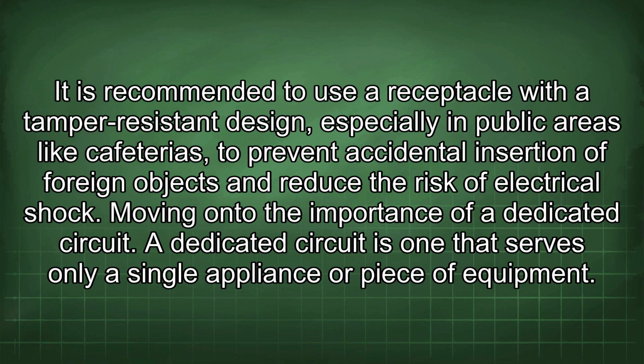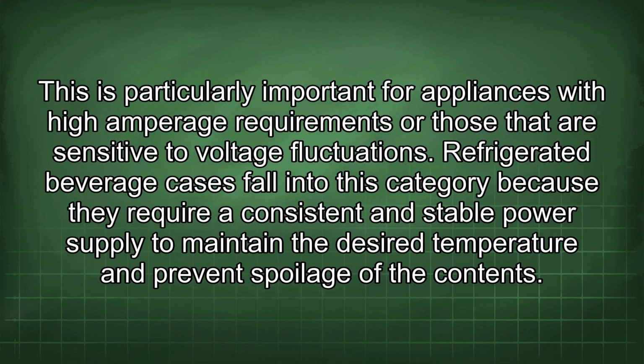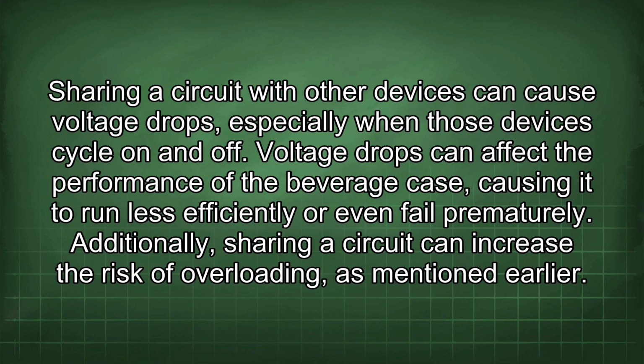Moving on to the importance of a dedicated circuit. A dedicated circuit is one that serves only a single appliance or piece of equipment. This is particularly important for appliances with high amperage requirements or those that are sensitive to voltage fluctuations. Refrigerated beverage cases fall into this category because they require a consistent and stable power supply to maintain the desired temperature and prevent spoilage of the contents. Sharing a circuit with other devices can cause voltage drops, especially when those devices cycle on and off.